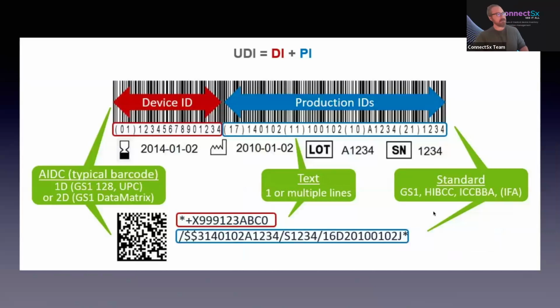So moving on, we have another example, another GS1 UDI up here. So you can see where these parentheses are. These would be identifiers that tell, according to the GS1 UDI standard, which again is like the formatting of how they build their UDIs, these parentheses sections are really important because that is the identifier for what follows. So it's telling whatever system is reading it that, this is the device ID, and it'll contain the catalog number and the labeler ID.